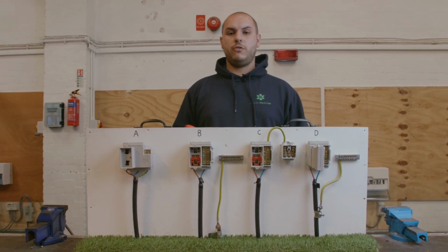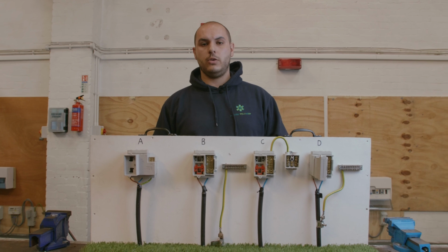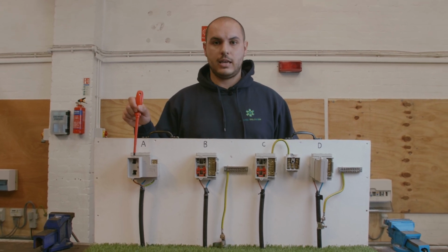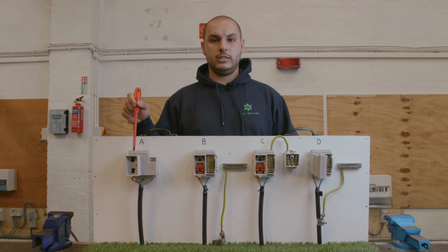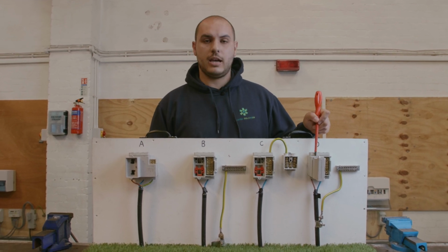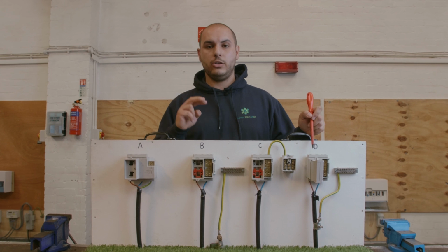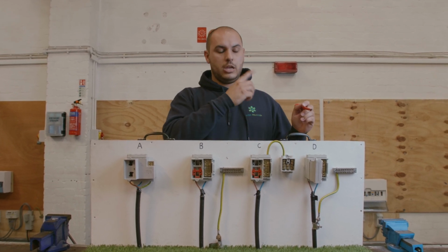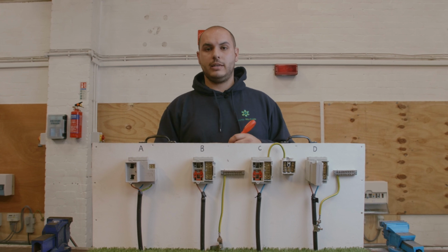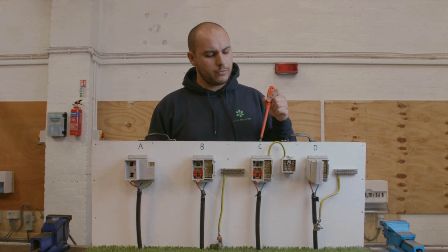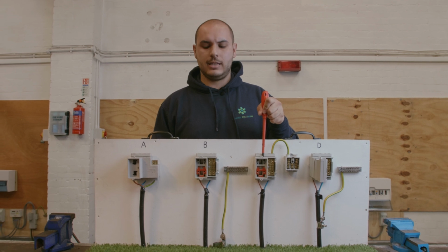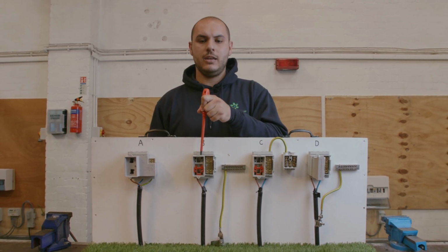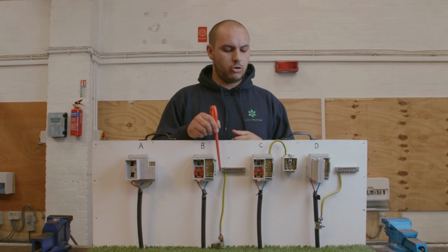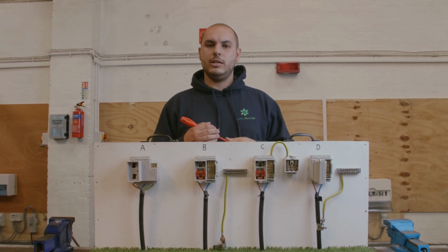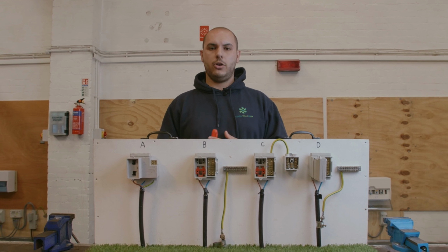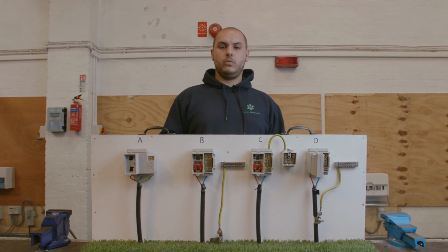So we've looked at a few different variations of the earthing arrangements within the UK. So like I mentioned, we've got the TNS that side, where it's got the 3 cables coming in separately. We've looked at the TNS that side, which has the 2 cables coming in, the line and neutral, and using the sheathing, the armouring on the supply cable as the main earth. And then we've looked at the PME or TNCS, and we've also looked at the TT there. So obviously the TT has an earth electrode, and the TNCS or PME is where you've got your combined neutral and earth. There is only one other variant which you may come across.